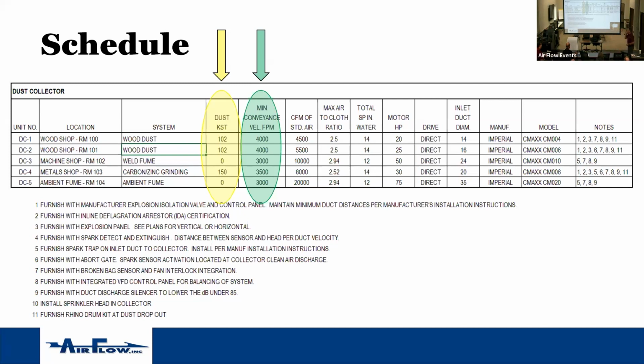Also drop in what your minimum conveyance velocity is. That is all tied to what your type of dust is. Lighter fumes will need a slower conveyance speed to be carried through the collector. Heavier wood dust and heavier metals will need a faster feet per minute to be carried back.